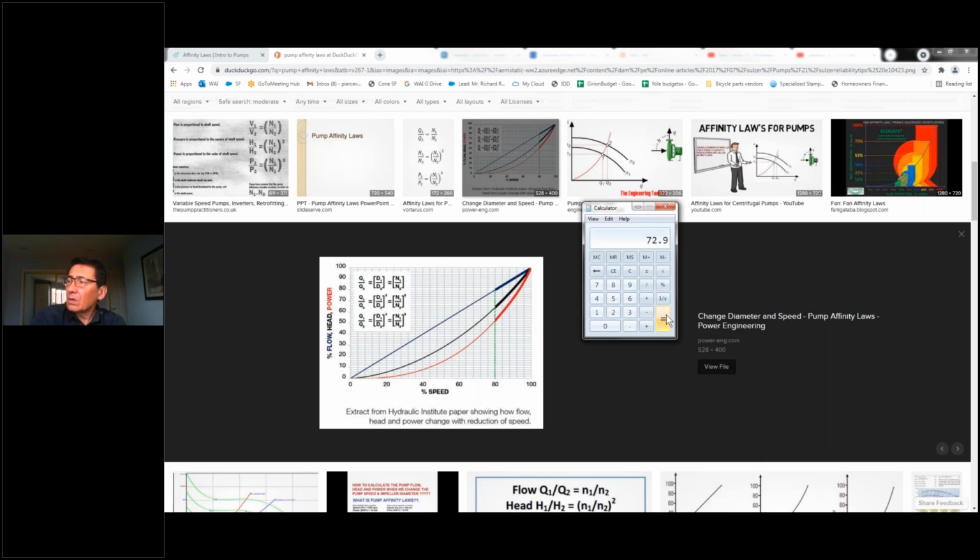So, most applications do not run at peak power, at peak requirement all the time. Now here's a note. If you do have an application that's always going to run full gate all the time, don't use a drive. Just run that thing on a contactor. Put a soft start on it to reduce the power inrush.